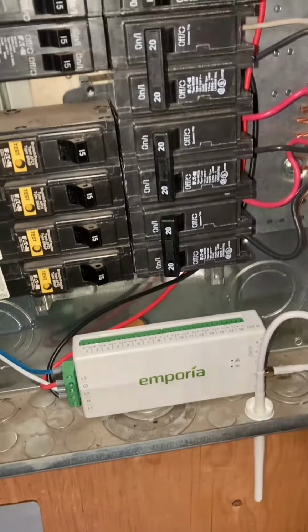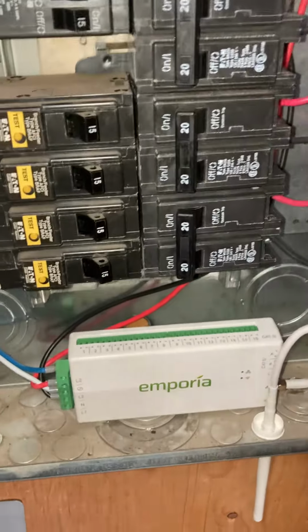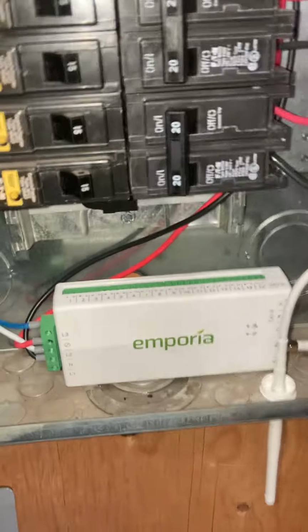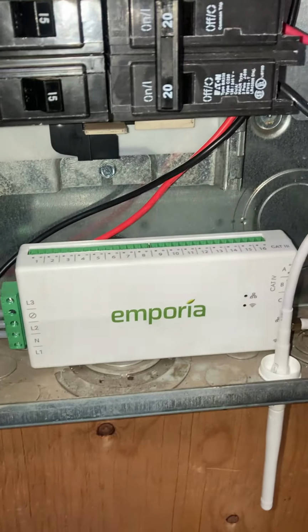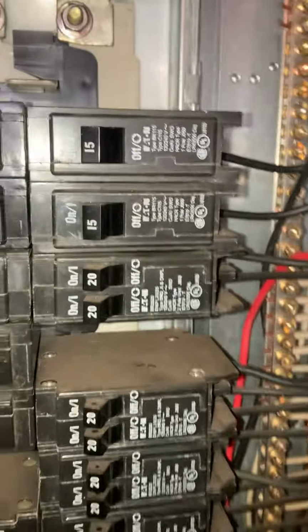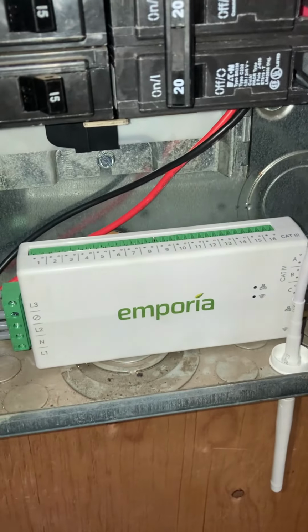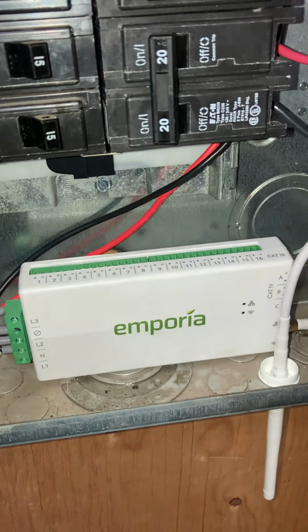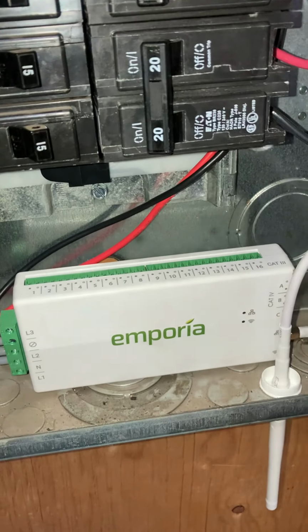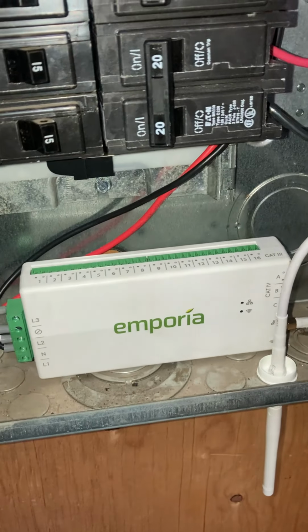We're not done yet, but if we wanted to test it, we could turn the power back on and we should get some lights on here. Turn those 2 breakers back on, then your main, and you should get some lights down here. If that works, we know we've done our job right, and then we'll shut everything off and start hooking up the CTs.